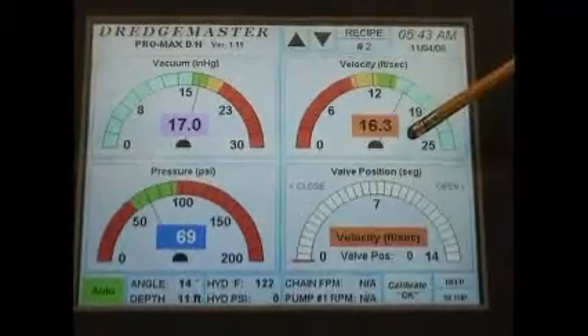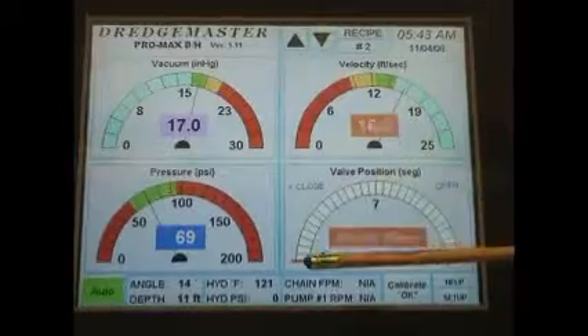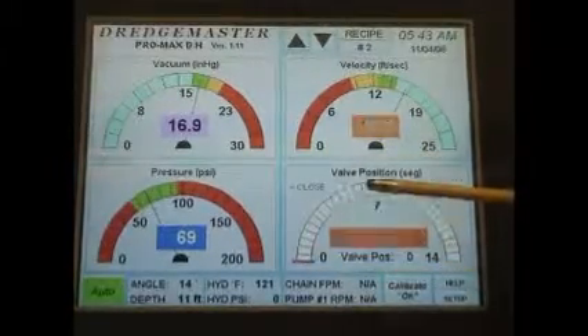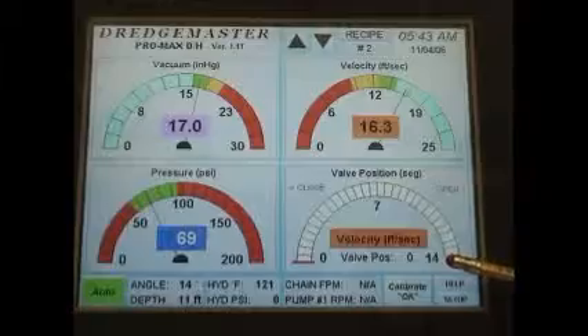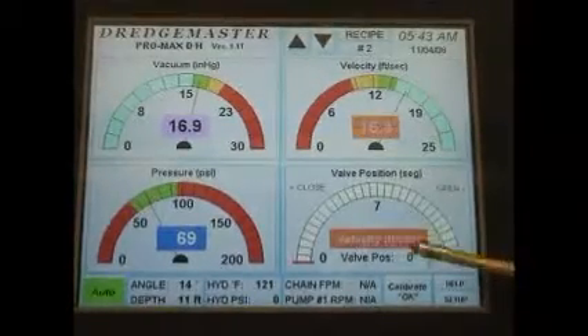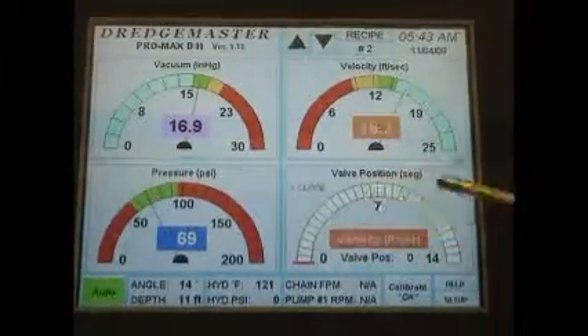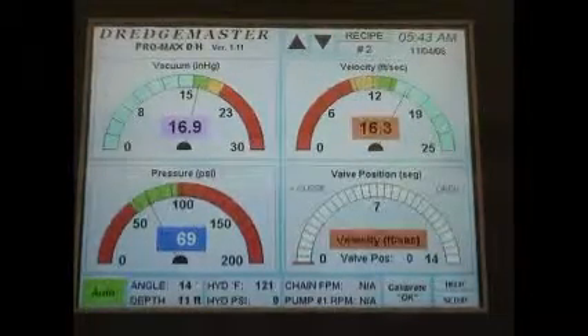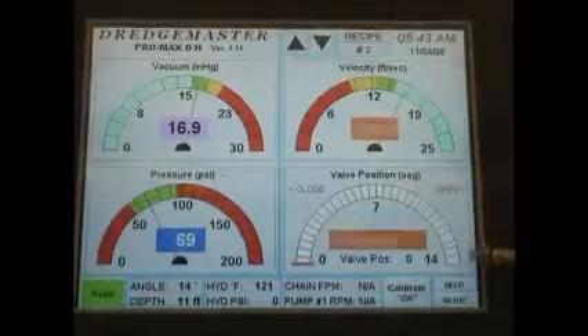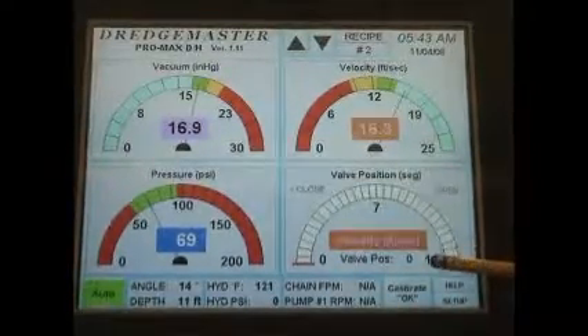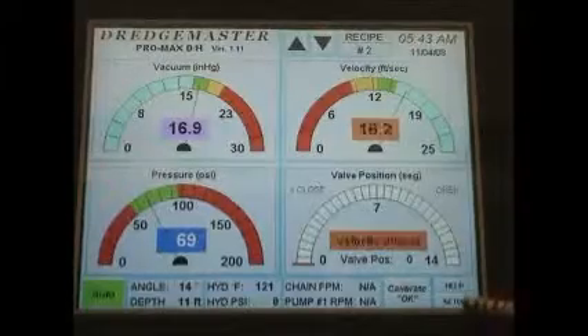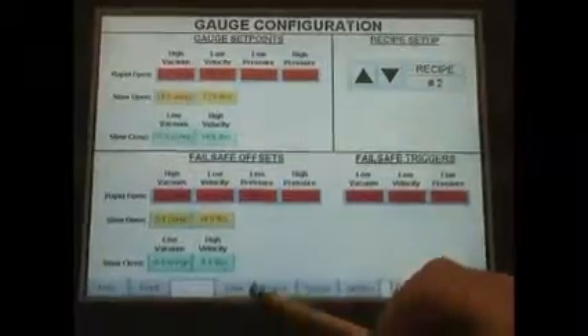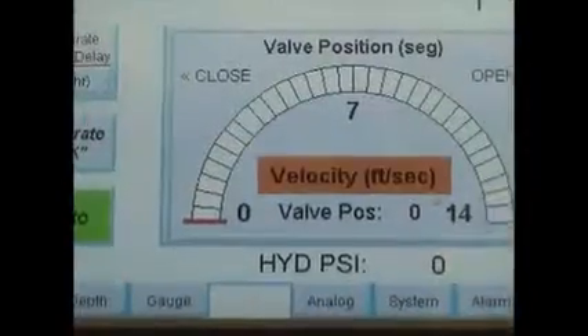Okay, the valve has the ability to increase or decrease how fast you want the valve to open. Right now the valve is set to open at 14 segments. So it's going to take 14 of these hits to go from fully open to fully closed. Let's say we want the valve to open a little slower, or we want more segments for the valve to open up. We want to increase that 14. We're going to touch the setup button here, and we're going to go to our valve button down here at the bottom. So we're going to touch our valve. We are now in our valve configuration screen.